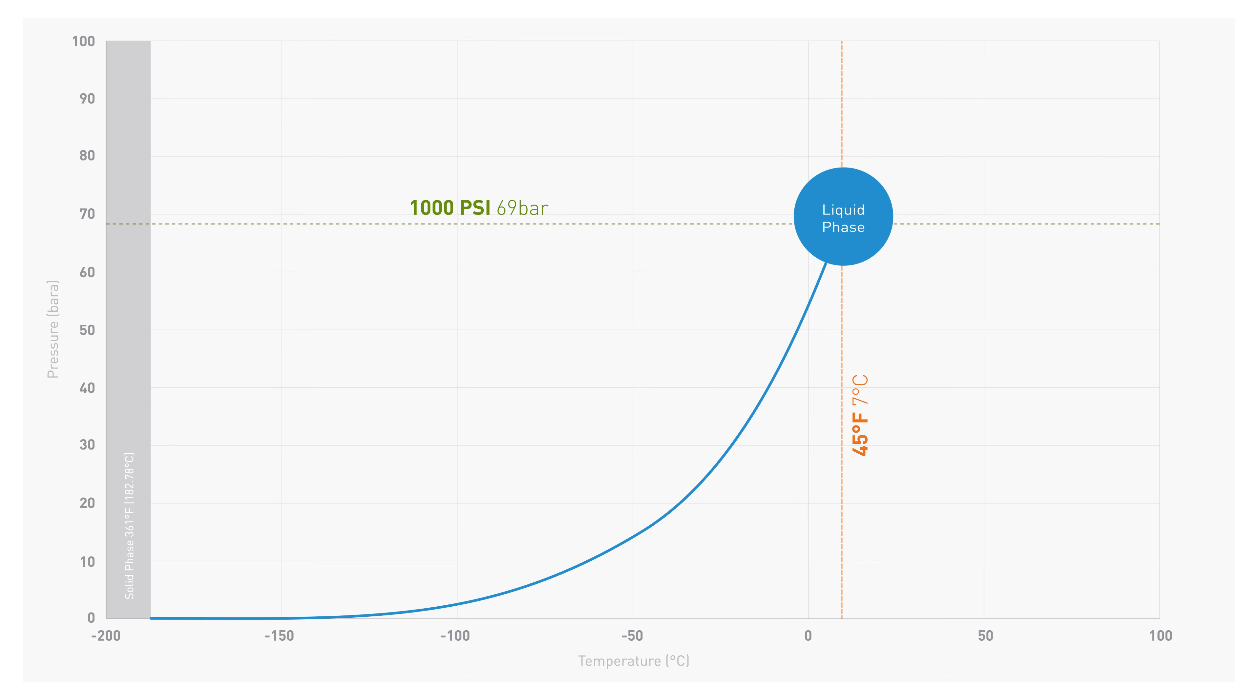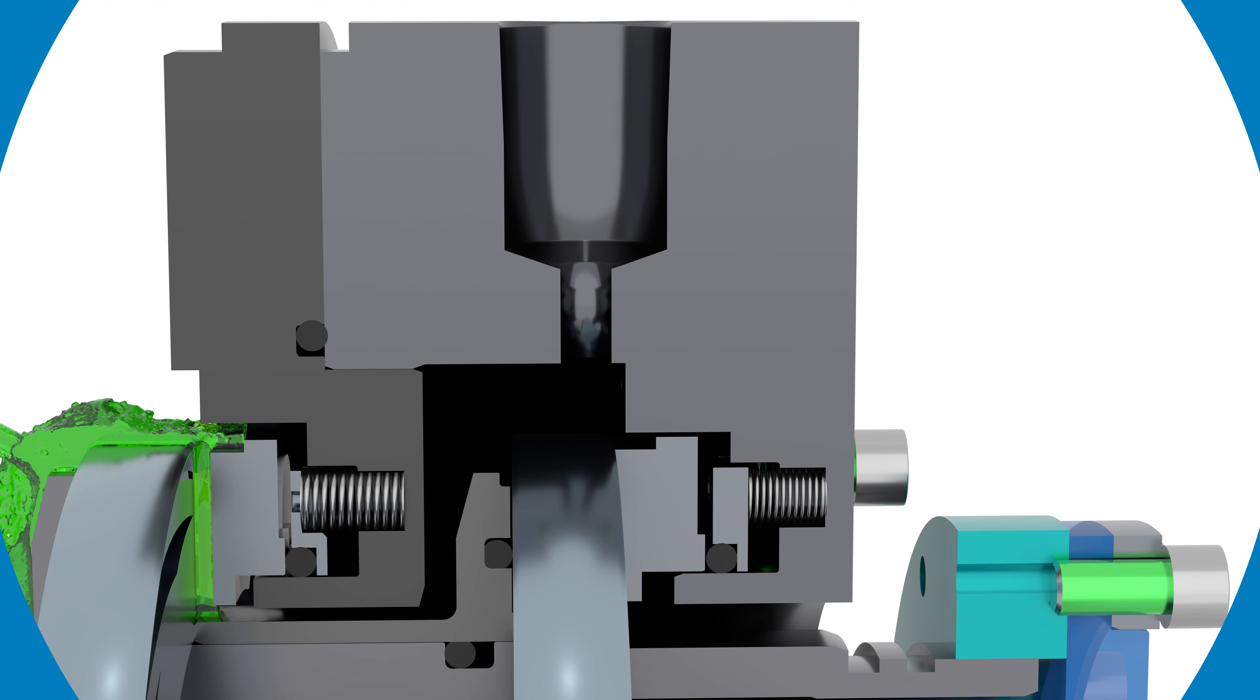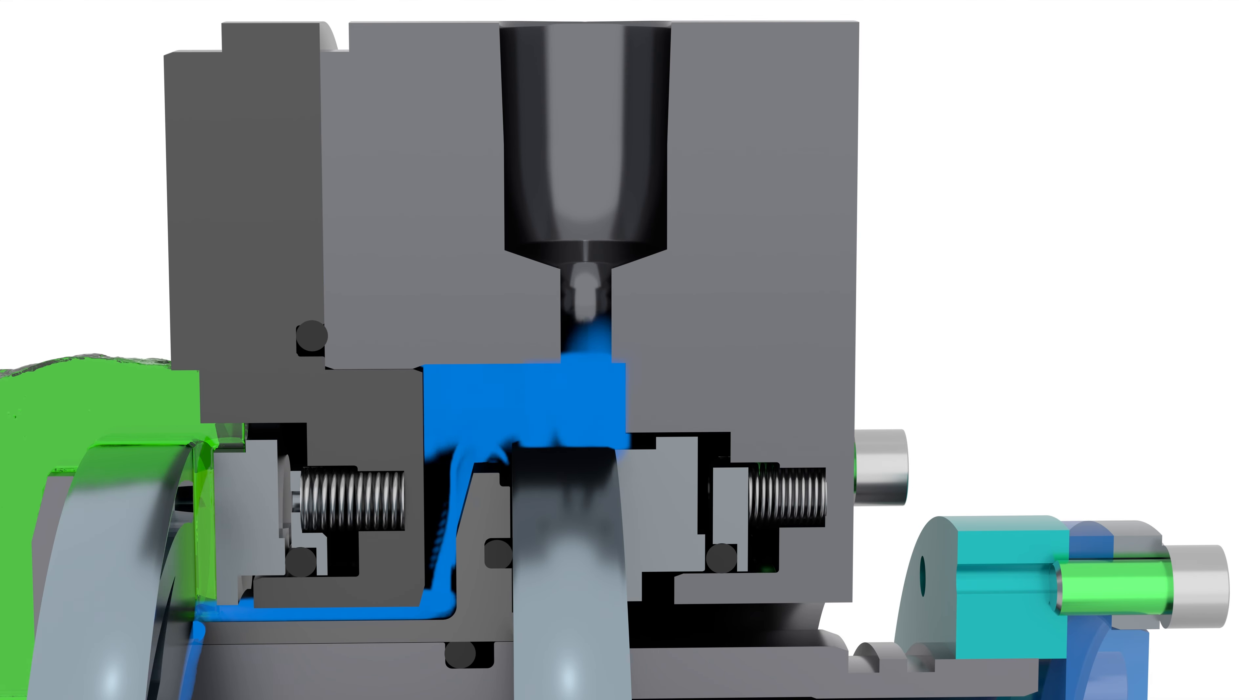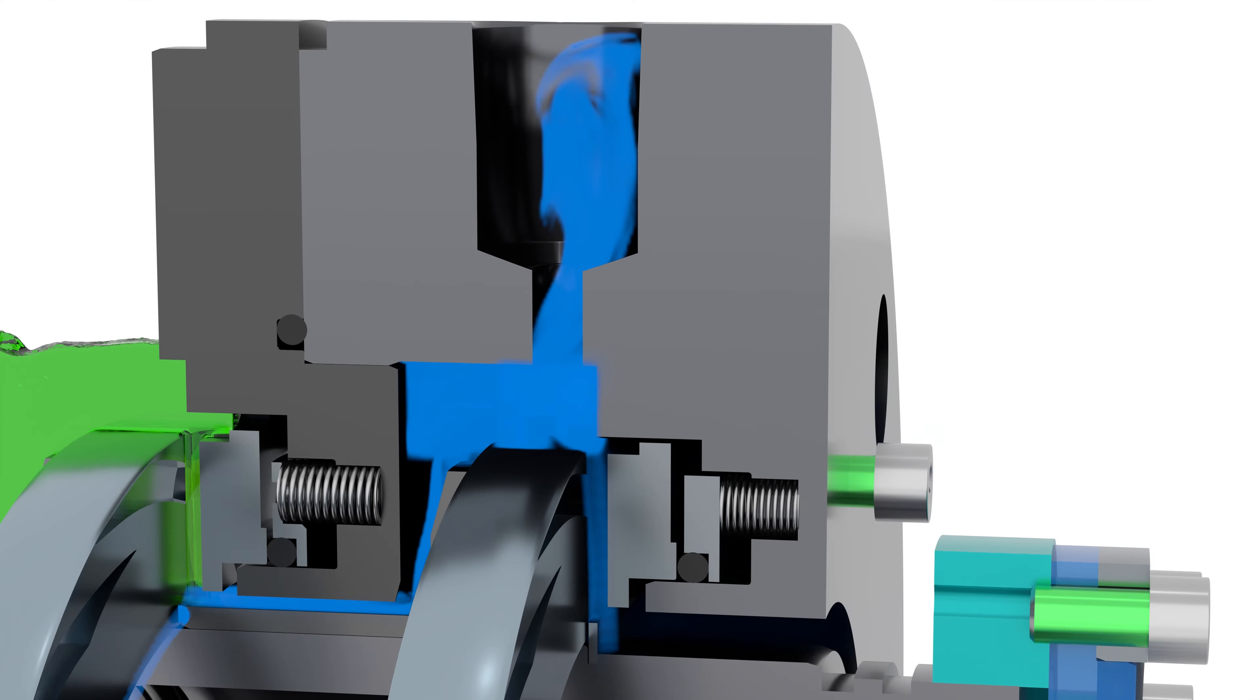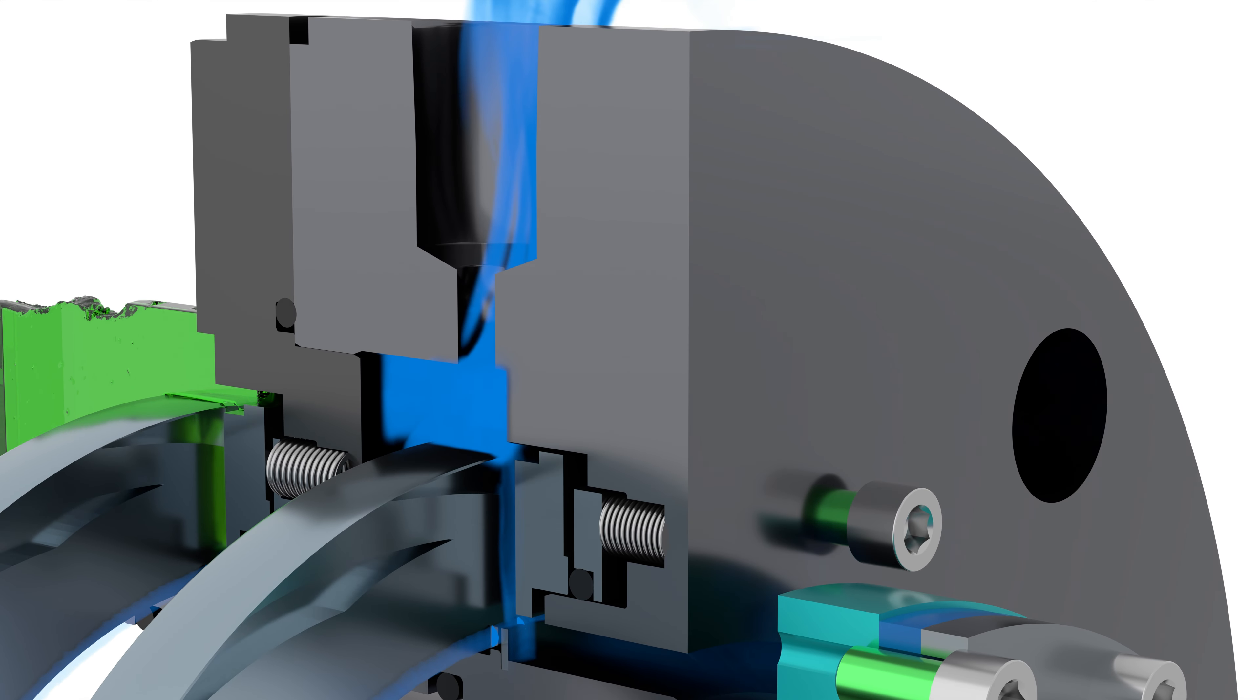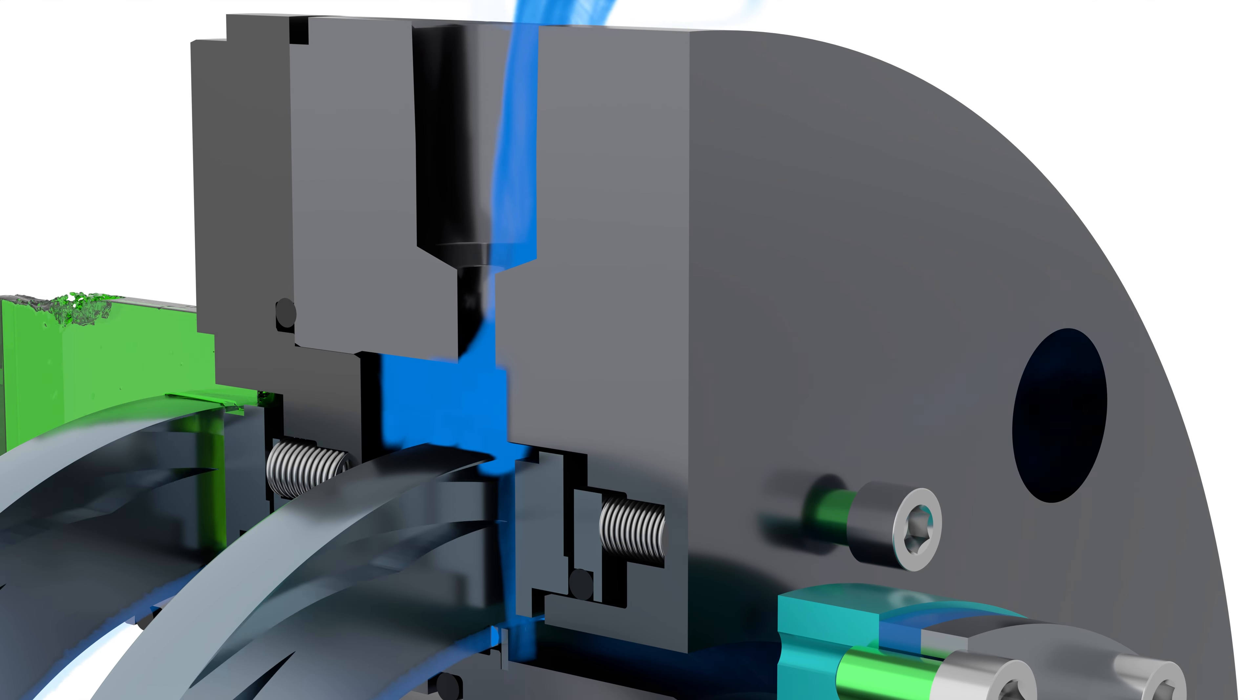When ethane crosses the seal face in liquid phase, a pressure drop occurs. This creates a phase change, forcing a small volume of ethane to vaporize, move to the vent tube, and onto a vapor recovery system.